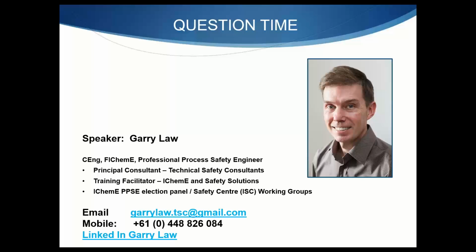I've got one comment here and then what looks to be one last question. So first of all, great presentation. Thanks, Garry. Just to note, having insulation on external bridle does not necessarily guarantee similar temperatures within the main insulated tank, since there is no flow and we rely on conduction via the upper and lower nozzle. And this is important to consider. If there is a change in process temperature in the main tank, there will be a delay. So it's just a comment. Yeah, that's fine. I agree.